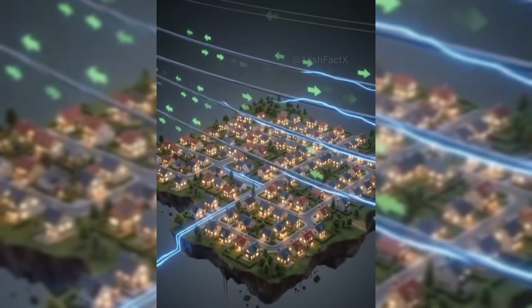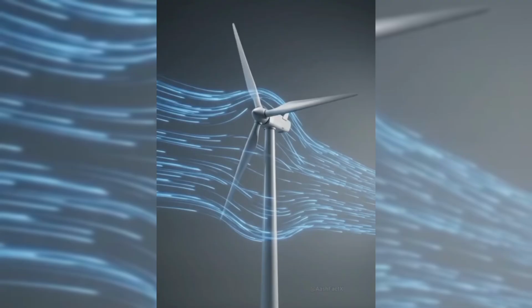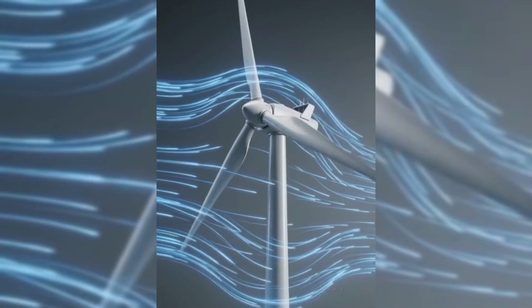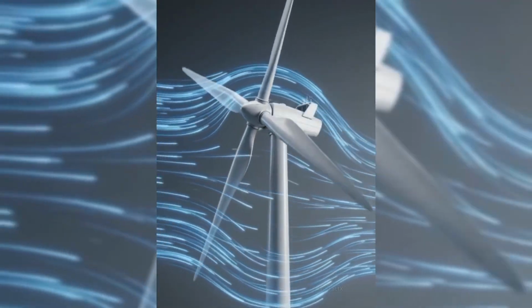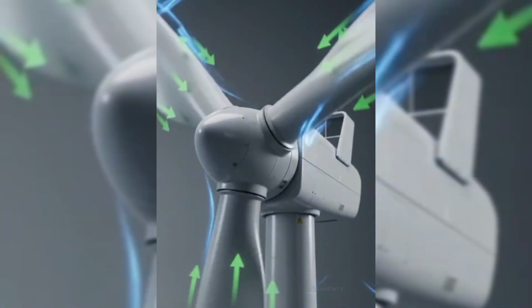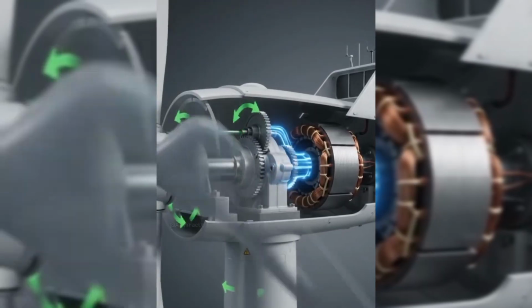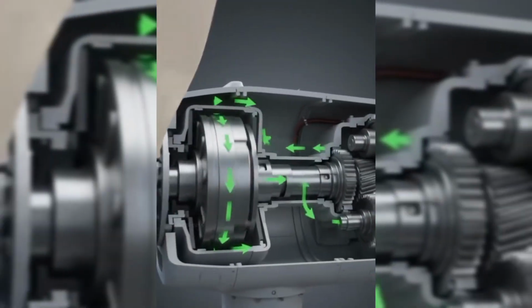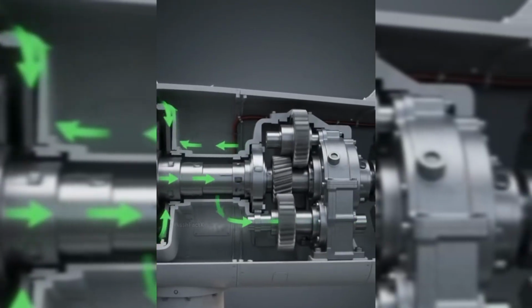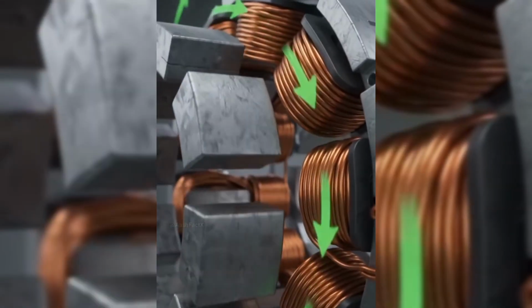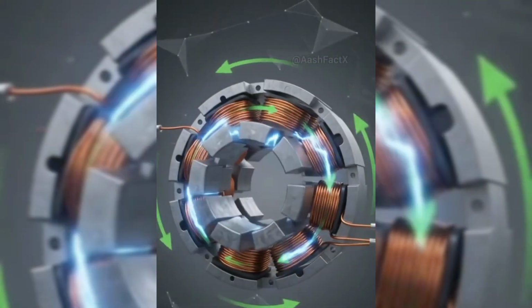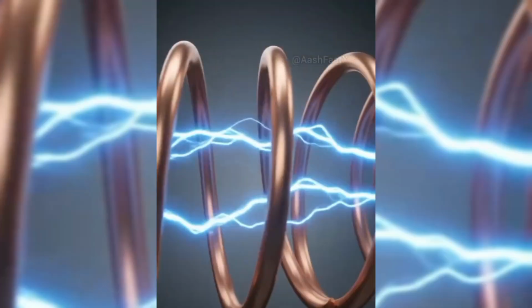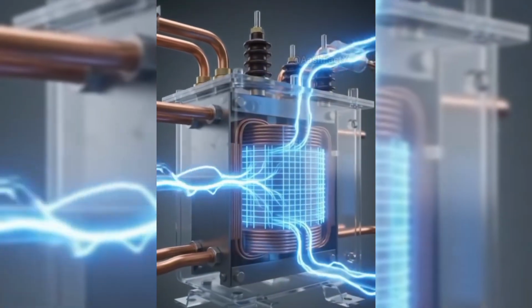This stream of moving electrons constitutes an electric current. Thus, the mechanical energy captured from the wind is officially converted into clean, alternating current electricity. However, the journey of the newly generated electricity is far from complete. The electricity exiting the generator is typically produced at a relatively low or medium voltage, usually around 600 to 1000 volts. Sending electricity through power lines at low voltage over long distances is extremely inefficient.